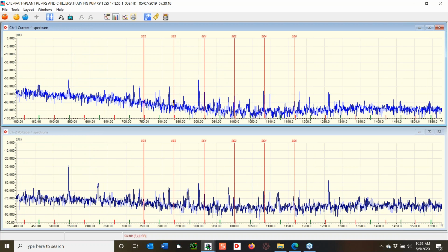Okay, very possibly. It lines up very, very close to line frequency. And if I want to verify it, I'm getting close, because one of these is line frequency and one set is not. So I come down here. The other thing I want to do is say this is showing me 74 dB down and this is showing me 69 dB down. This is taller. The lower number means taller. So this is just a power harmonic. Boom, done. If my voltage is higher, it's from outside the machine, upstream, so it'd be VFD related. If it's higher in current, it's the machine.